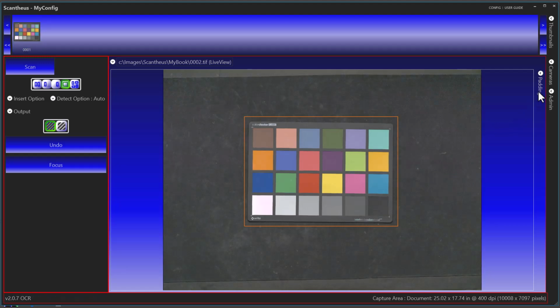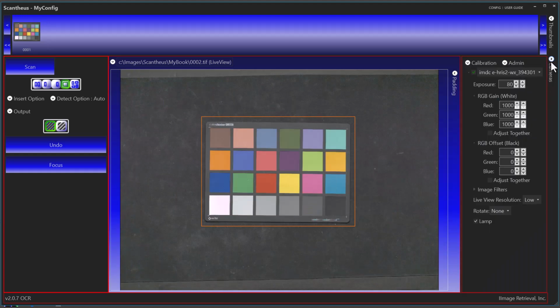So our scanned image pops up in the thumbnail, but let's go into the camera expander here, and this is where you will find the calibration. There's only 7 camera settings that are affected by calibration. That's exposure, RGB gain, and RGB offset, that is, gain has red, green, and blue components, and offset has red, green, and blue components. The gain affects the white patch or the lightest patch. The offset affects the black patch.